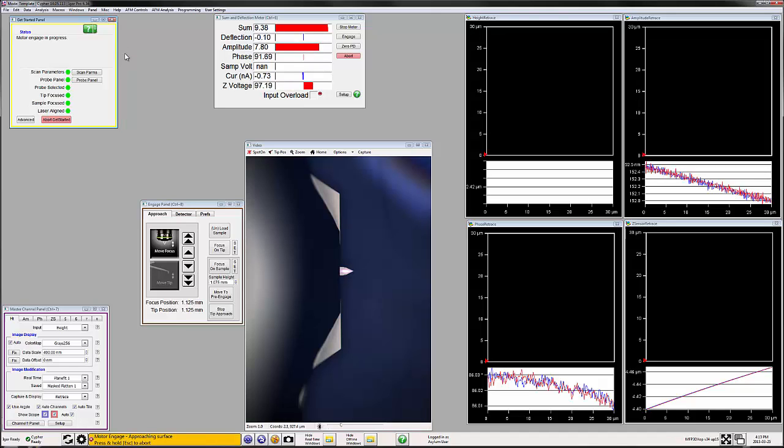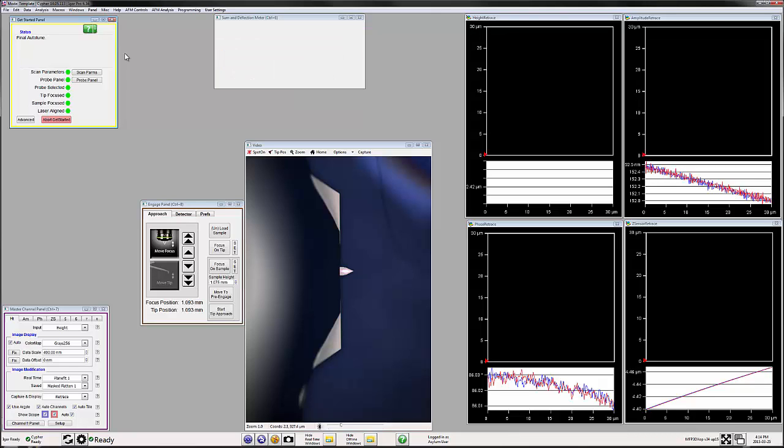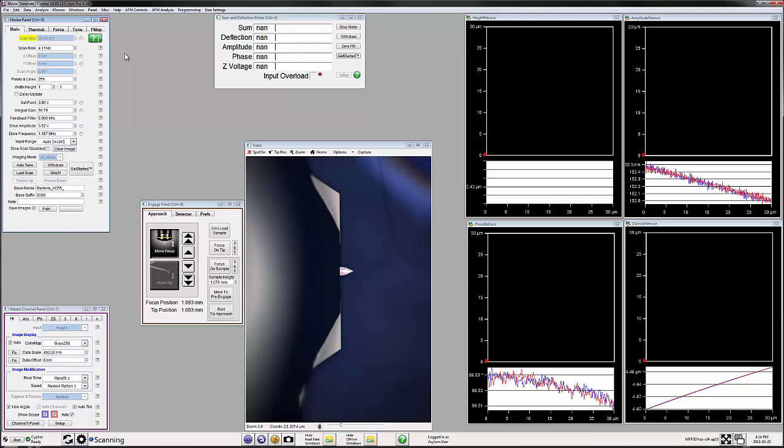After the GetReal calibration and first auto-tune occurs, the AFM will automatically start to engage onto the sample. With the Cypher AFM, the motors will move the tip to a set distance above the surface, and then it will auto-tune the cantilever. The AFM will then begin to search for the surface until it engages, and of course, right after that, we'll do the last auto-tune. After that, the scan begins and the Get Started panel disappears until you need it again.